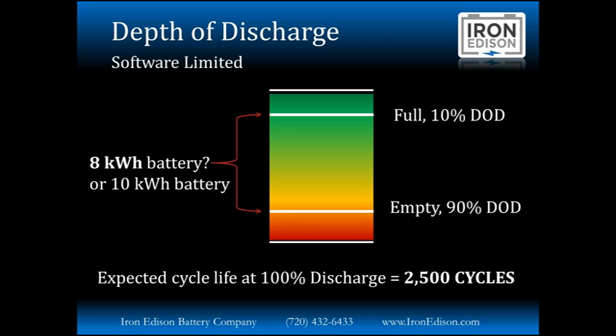So we're happy to help compare and contrast different spec sheets from different manufacturers to help you understand the difference between true depth of discharge and software limited depth of discharge. A lot of our specifications will say, okay, this battery is going to have, say, 1,000 amp hour total capacity, and then at a certain depth of discharge, you can expect this amp hour capacity or this amount of kilowatt hours. So we probably give too much information. It can be a little overwhelming and confusing, but we want you to know exactly what you can expect out of a battery from Iron Edison.